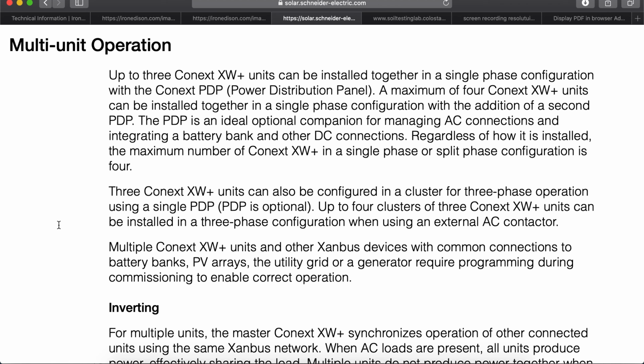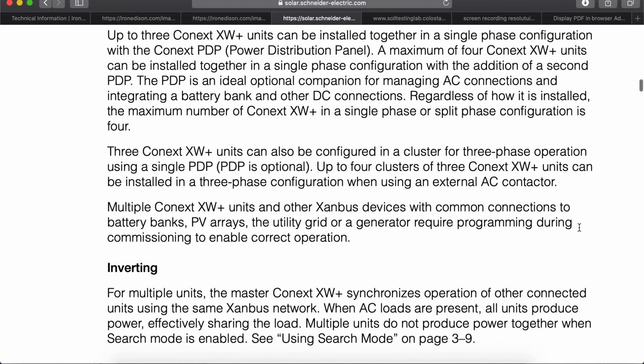3 XW Plus units can also be configured in a cluster for 3-phase operation using a single PDP. Up to 4 clusters of 3 Conext XW Plus units can be installed in a 3-phase configuration when using an external AC contactor. This is exciting stuff. I've done a system like this and it is beautiful.